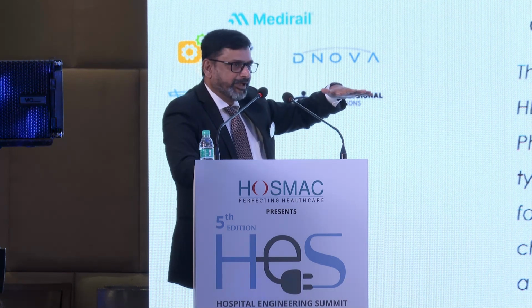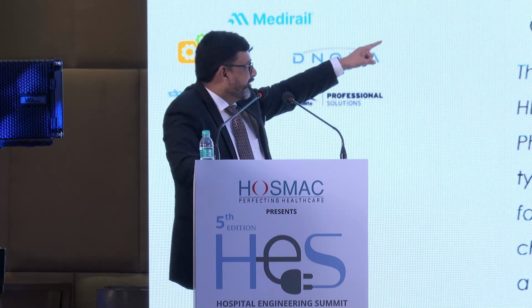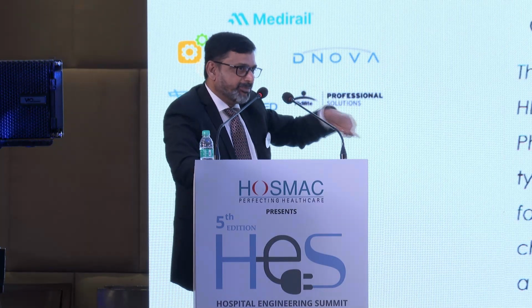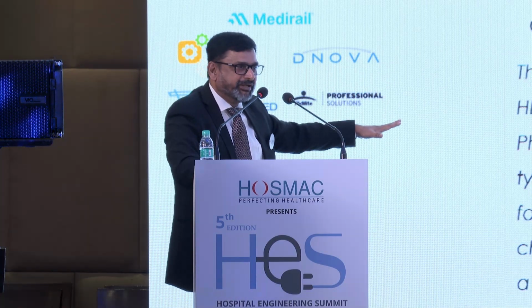As I said, the pharma industry of India is very good at this, which we call DOP testing, dioctyl phthalate testing, wherein an aerosol is applied on top of the filters, and we check for filter media damage. Sealant to frame, any bypass because of gasket leakage, frames and grids are also tested. The same thing needs to be followed. We save quite a bit of money there, but if this integrity is not checked, it is useless. If the HEPA filters are not tested, pressure differentials are not monitored, and we don't do DOP testing of these filters at regular intervals, we will not be in a position to say that it's a robust design.